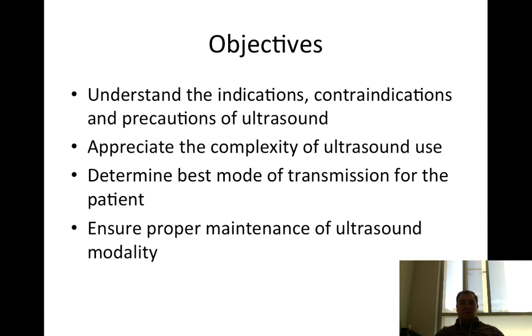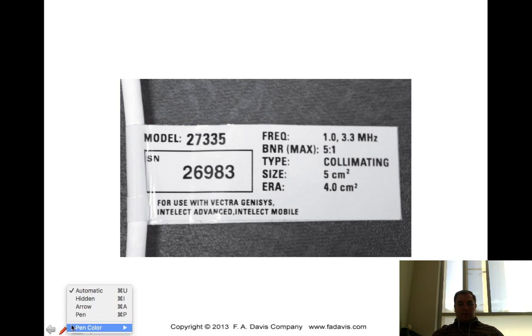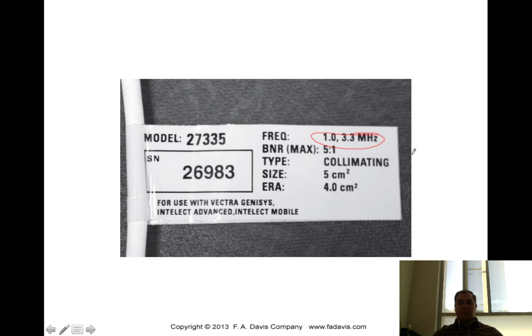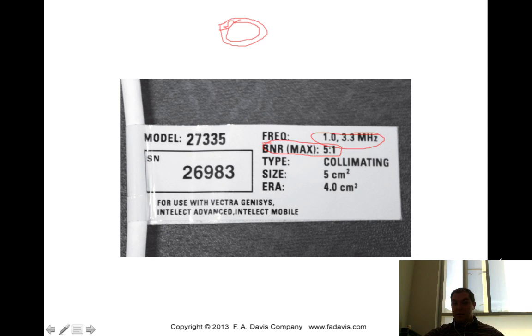You can see the objectives for today's lecture. This first picture shows an ultrasound unit. It talks about the frequency — 1 or 3.3 megahertz — the BNR, the max BNR. This BNR is a 5-to-1 beam non-uniformity ratio. It also lists the size of the ultrasound head at 5 centimeters squared, and the effective radiating area of 4 centimeters squared. This is a Vectra Genisys, a Chattanooga model.